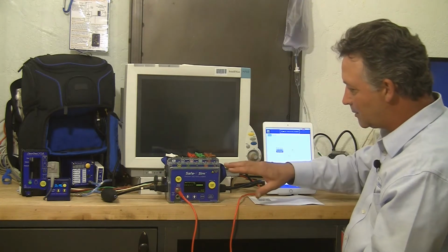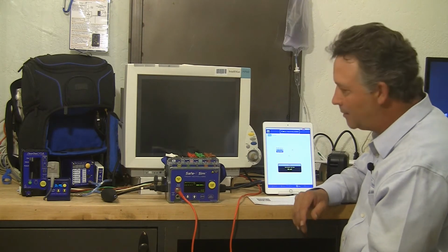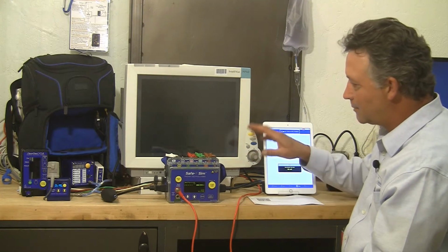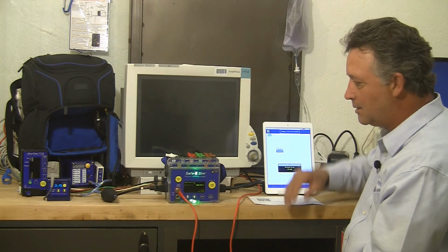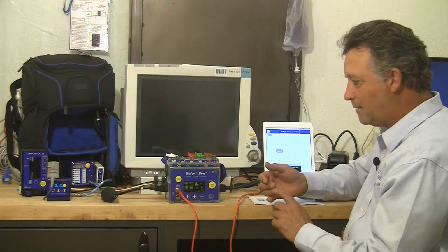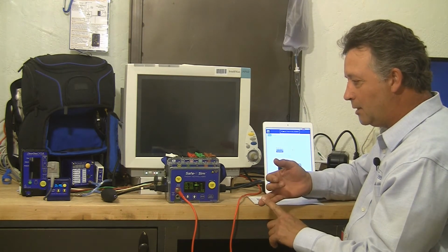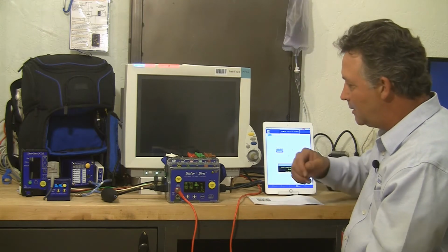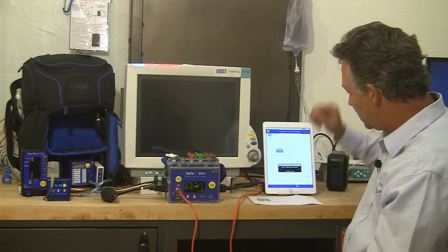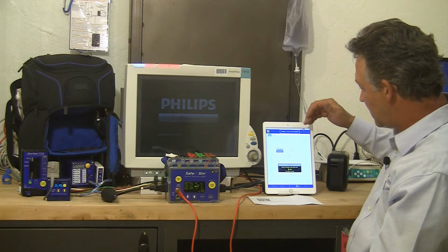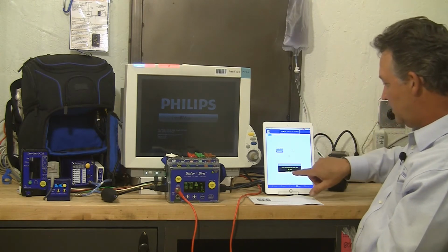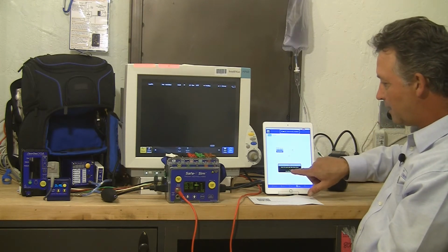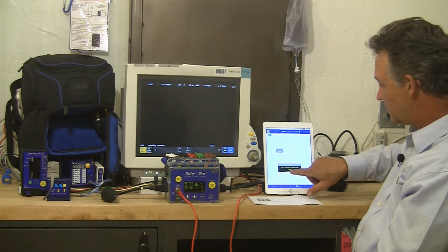It's going to automatically start my electrical safety tester, which is going to run a series of electrical safety tests for this device that can be defined by the user and/or can be driven by the CMMS system, depending on how you set that up. So we're running electrical safety tests right now from our iOS device, and we're actually getting real-time measurements back via Bluetooth while those tests are occurring.